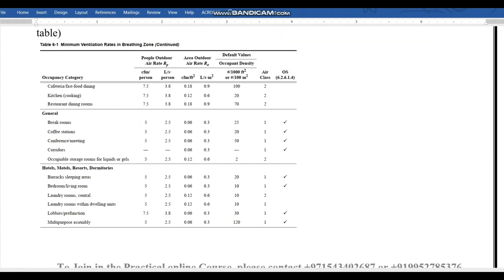First of all you need to know the difference between fresh air and exhaust air tables. Second thing is how these values are decided. The minimum CFM per person should be 5 CFM. It will vary from 5, 7.5, 10, and 20 based on the application, but minimum should be 5 CFM per person.